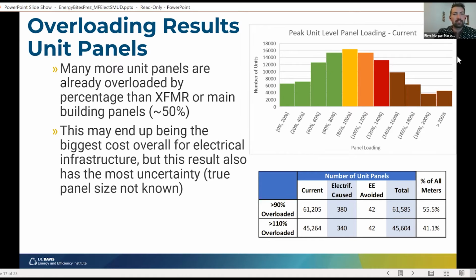And that's really where the biggest cost concern is, because if you have to replace the panel in every single unit when you do an upgrade, that's really going to jack up the costs of these projects. So this could be the biggest infrastructure cost. But again, there's a lot of uncertainty, and it's really hard to say before you go into a building whether or not you're going to need to do it. But I've tried to predict that here, and a lot of these buildings are overloaded. But again, not many are caused by electrification. A lot of them were just already overloaded.